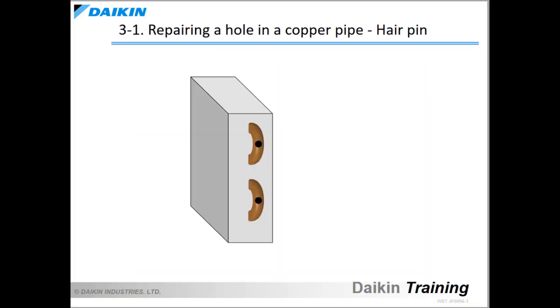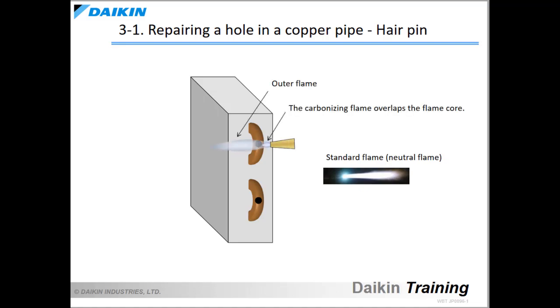Next, let's learn about the repairing method when there is a hole in the hairpin. Use the neutral flame where the carbonizing flame overlaps the flame core. Move the flame core closer to the hole and heat only the area around the hole. The area around the hole heats up immediately, so apply the brazing filler metal to fill in the hole.